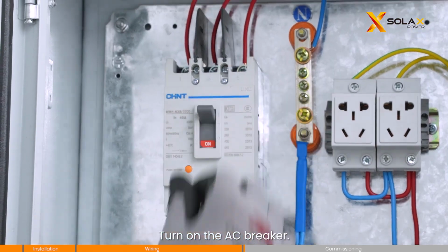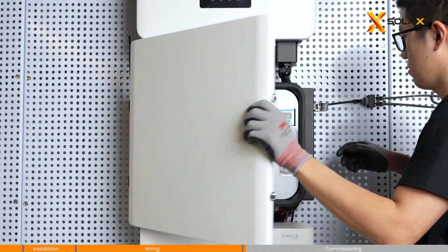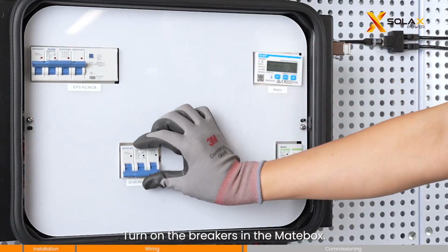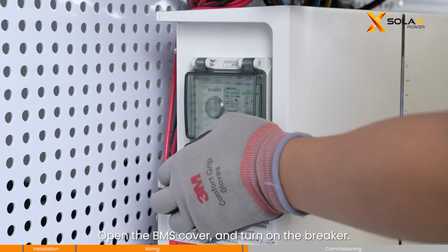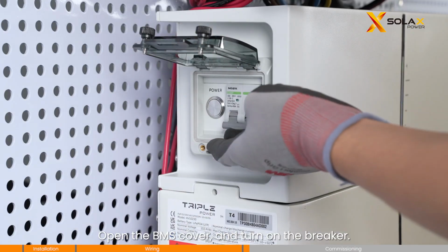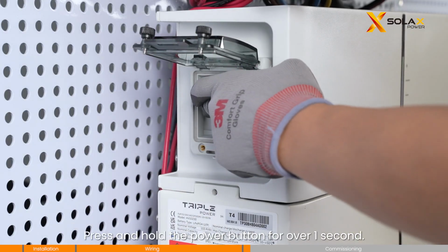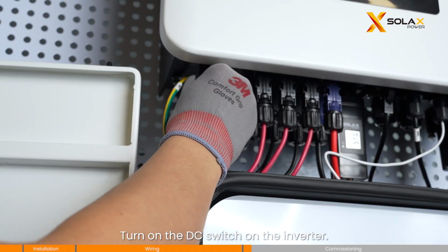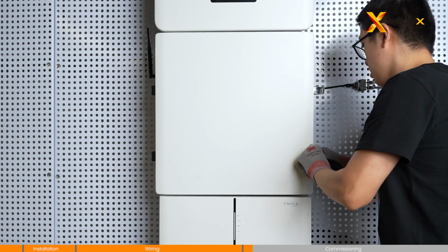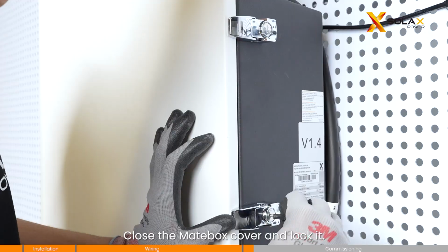Turn on the AC breaker. Turn on the breakers in the Matebox. Open the BMS cover and turn on the breaker. Press and hold the power button for over 1 second. Turn on the DC switch of the inverter. Close the Matebox cover and lock it.